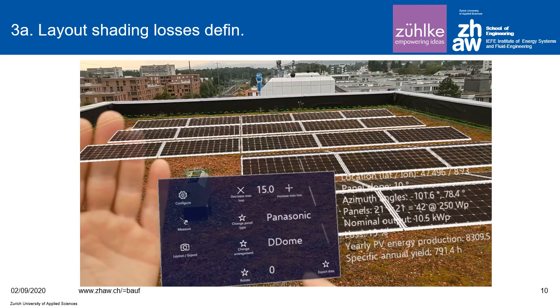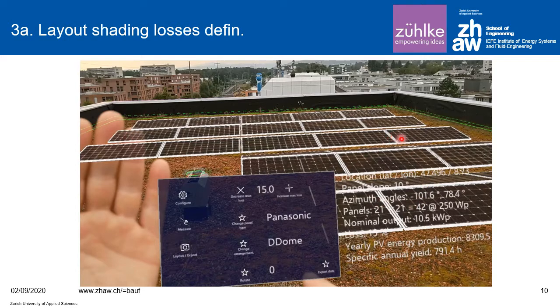Now we reach task 3, searching for the final layout of the PV modules. We choose the type of PV modules and the mounting structure. On the HoloLens screen we see the percentage of allowed shading losses due to the railing and other obstacles. In a few seconds, by changing these numbers, the system will automatically give us choices for positioning the layout of the PV modules.